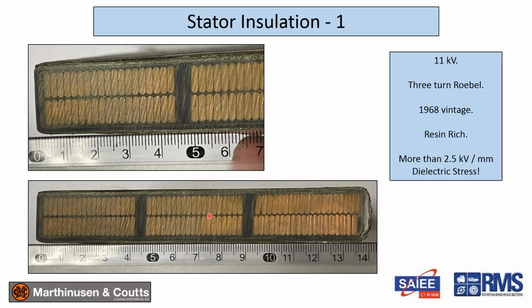This is a very interesting sample cross section. I keep it in my office. It's actually of one of the Kelvin 60 megawatt machines, and it was a failure brought on by a fault. It's 11 kV, about 1968 vintage. It's got higher than 2.5 kV per millimeter dielectric stress, and that's how long it lasted. Very interesting for the specialists here. It's a 3-turn Roebel bar, so it's quite rare.